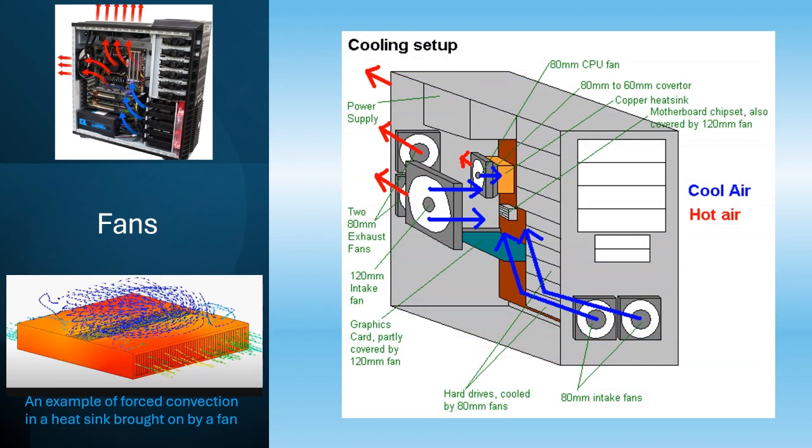Fans accelerate airflow, which consequently accelerates the dissipation from the heat sink by optimizing the convection stage. This, of course, increases system reliability and performance. Adding fans to a CCS can easily increase heat dissipation by about 50%, which corresponds to a 10 to 20 degrees Celsius reduction in component temperature. The optimization challenges, however, have more to do with power consumption and noise generation trade-offs.